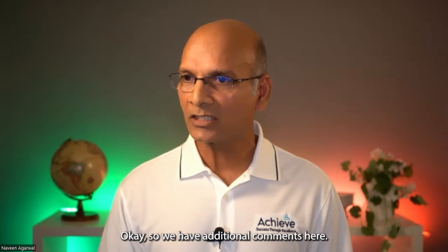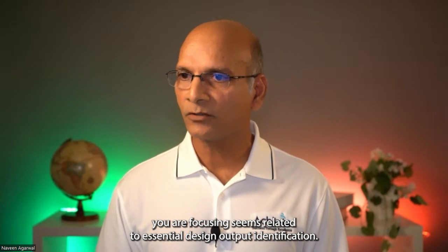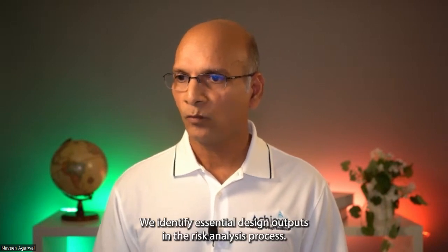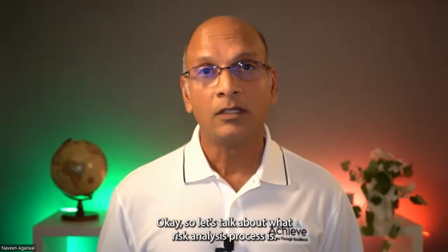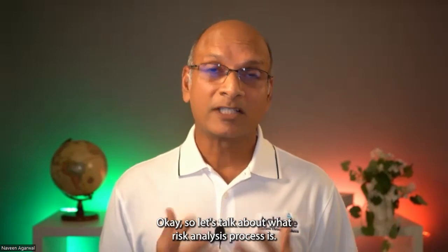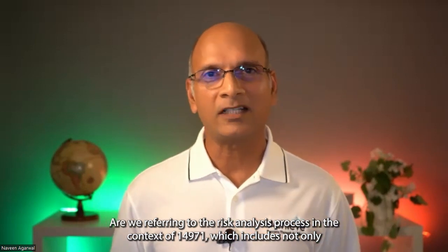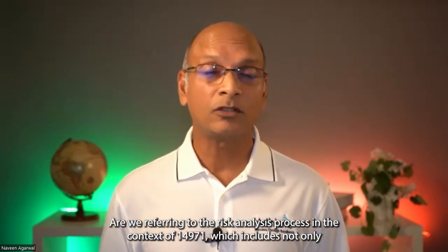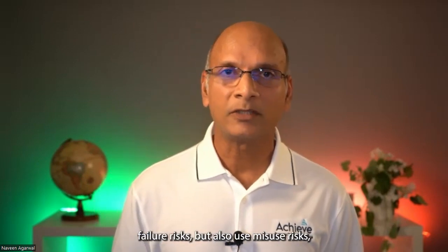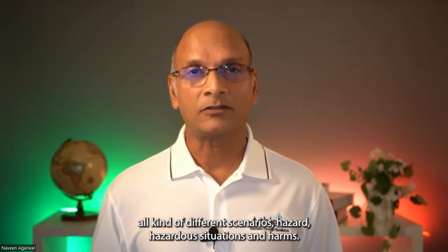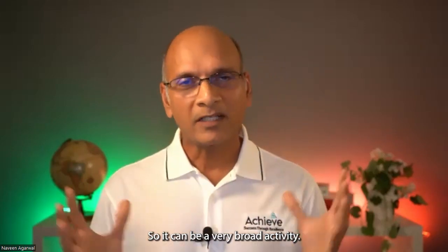Okay, so we have additional comments here. John, you are saying that the design output linkage you are focusing seems related to essential design output identification. We identify essential design outputs in the risk analysis process. Okay, so again, let's talk about what risk analysis process is. Are we referring to the risk analysis process in the context of 14971, which includes not only failure risks, but also use-misuse risks, all kind of different scenarios, hazardous situations and harms, sequence of events. So it can be a very broad activity.